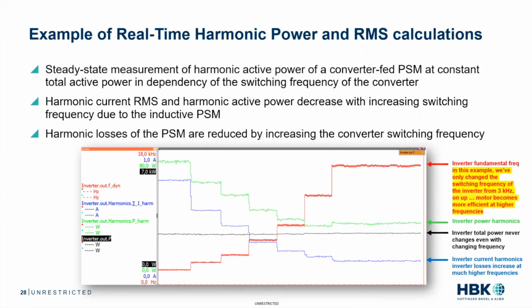You see that the inverter current harmonics, basically a motor becomes more efficient as you increase the frequency. However, the inverter becomes less efficient as you increase the frequency. You've got inverter losses. So you need to make a compromise there. It's kind of a two-edged sword, but at least you have the information you need in order to make a better decision.